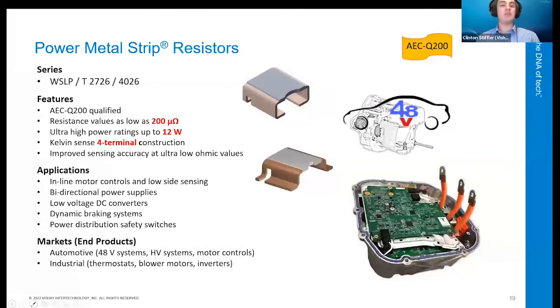The WSLP 2726 and 4026 offer extremely low resistance values down to 200 microohms, high power ratings of 12 watts, and the benefits of 4-terminal Kelvin termination. This improves current measurement accuracy and repeatability and provides improved TCR performance over a 2-terminal construction. The low TCR performance offers more stable current measurements over an ambient temperature range, and also with the temperature increase due to applied power.